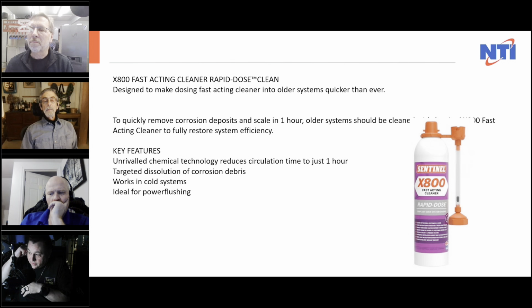So that's stuff we've got to look at when flushing these systems out. Every year when we pull that filter on a preventive maintenance, it should be clean, because remember, we don't have any of that magnetite being pushed around the system.